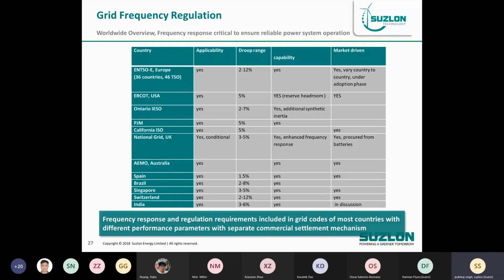So sometimes you will respond to false events. That is a big challenge, and that's why one has to do at least four, five or six cycle sampling and averaging, so that you take 20 millisecond measured values, take five values, wait for 100 or 200 milliseconds, do the averaging, and then you make a decision. Yes, it's a real low frequency event, and then your turbine or your park responds to that. But simply taking one value and responding would be a nuisance. This is our experience, at least, during feature development.